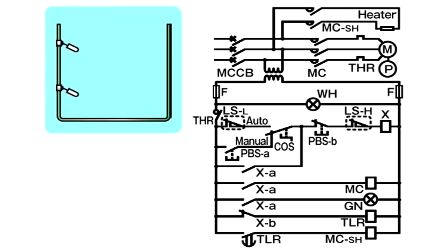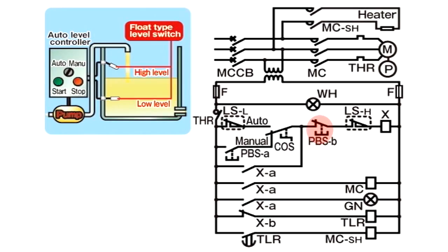Let's look at an example where the pump is stopped manually and then started again. The tank is about half full and the pump is operated in auto mode. At this time, L-S-H relay is on and the L-S-L relay is off. As P-B-S-B is pressed, current passing through X-A to P-B-S-B, L-S-H, and to X is cut, and X is demagnetised. In the subsequent sequence operation, X-A turns off and X does not remain in self-holding state, so pump operation comes to a stop.